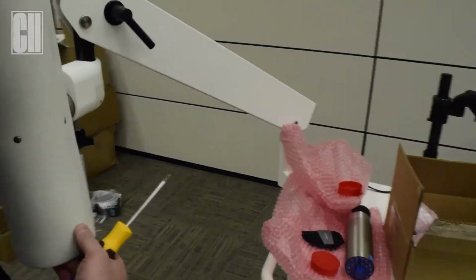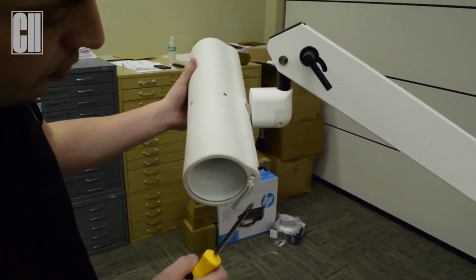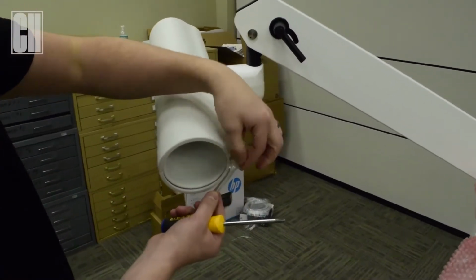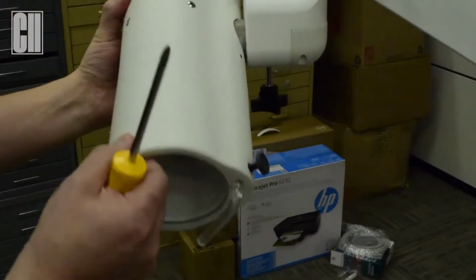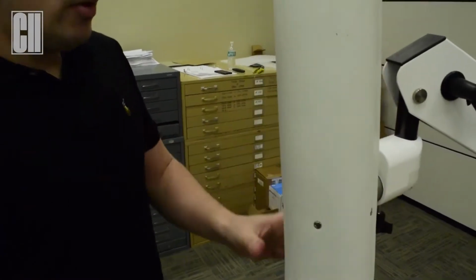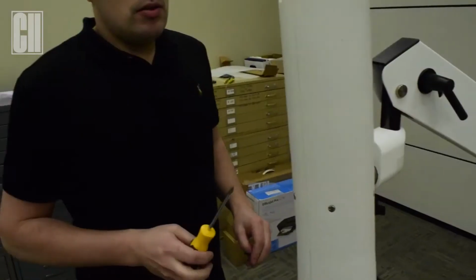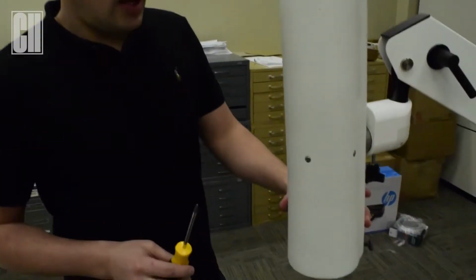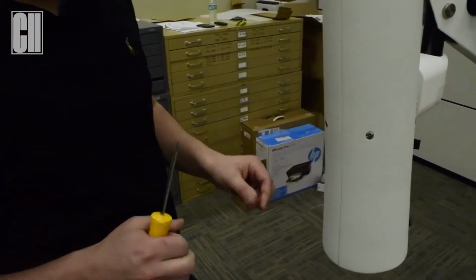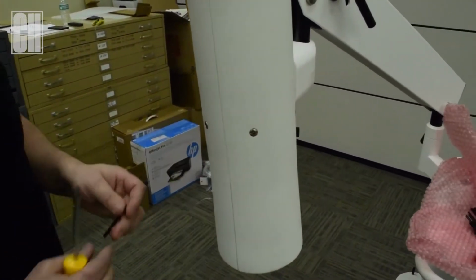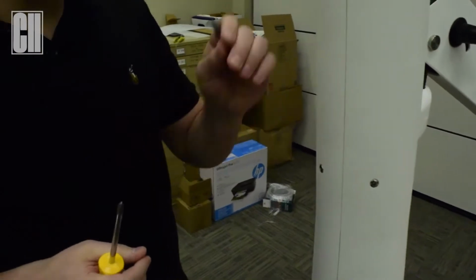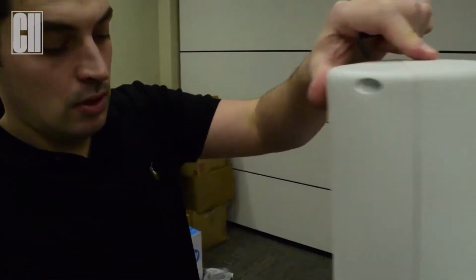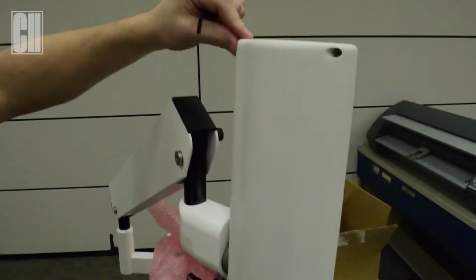So the easiest way to remove it is you want to remove the side that does not have the pointer rod on it first. So at this point, when you're looking at the system, you want to remove the left cover first. So at this point in removing the collimator casing, you'll need a Phillips head screwdriver to remove the 4 screws, and then you also need a 5/32 Allen wrench to remove the 3 Allen screws that are holding the casing together.